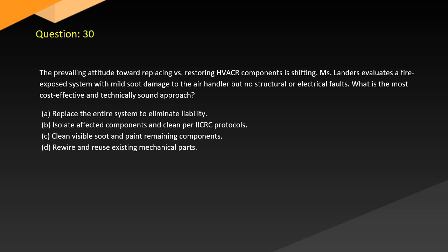Question 30. The prevailing attitude toward replacing versus restoring HVACR components is shifting. A technician evaluates a fire-exposed system with mild damage to the air handler but no structural or electrical faults. What is the most cost-effective and technically sound approach? A. Replace the entire system to eliminate liability. B. Isolate affected components and clean per IICRC protocols. C. Clean visible soot and paint remaining components. D. Rewire and reuse existing mechanical parts.